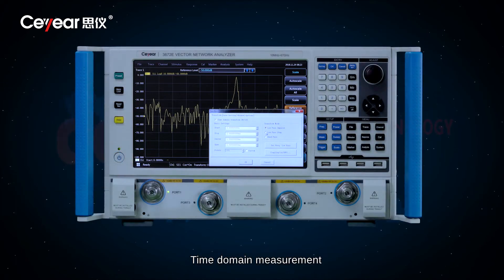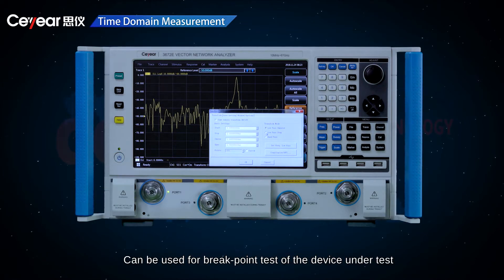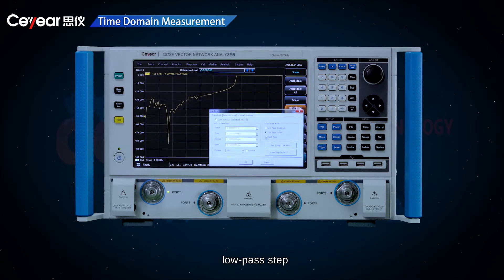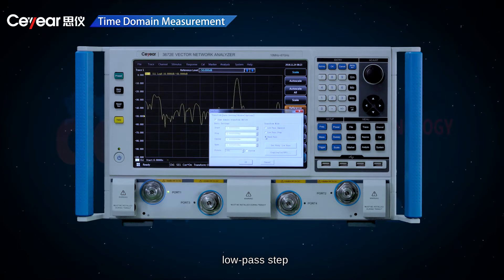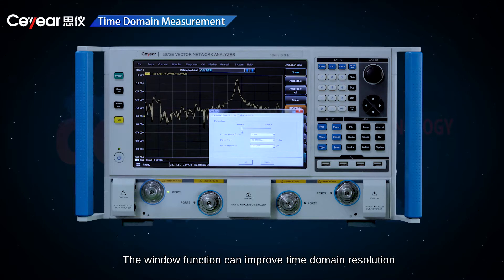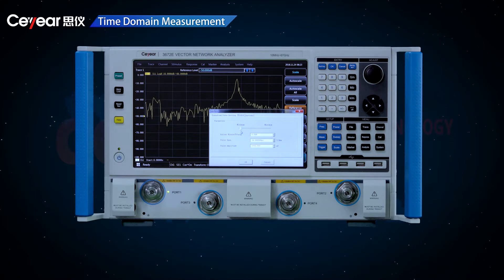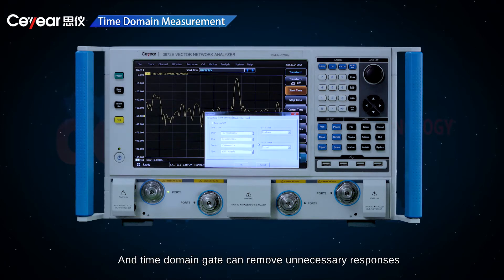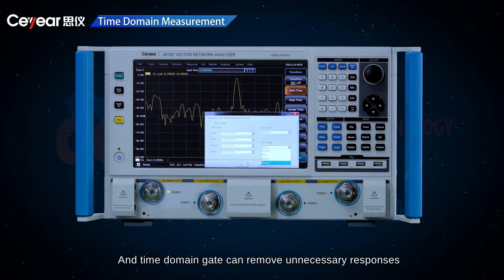Time domain measurement can be used for breakpoint test of the device under test, providing such measurement modes as low-pass impulse, low-pass step, and bandpass impulse. The window function can improve time domain resolution and reduce side-lobe effects, and time domain gate can remove unnecessary responses.